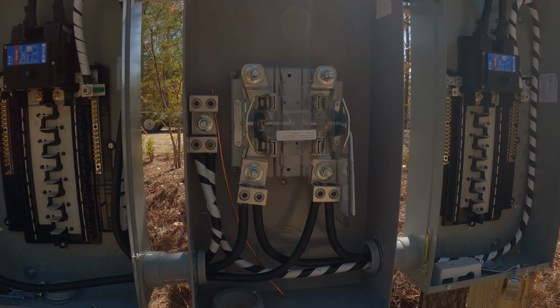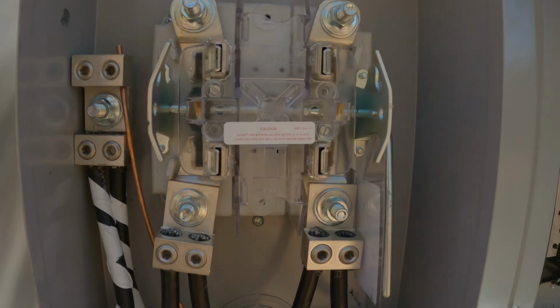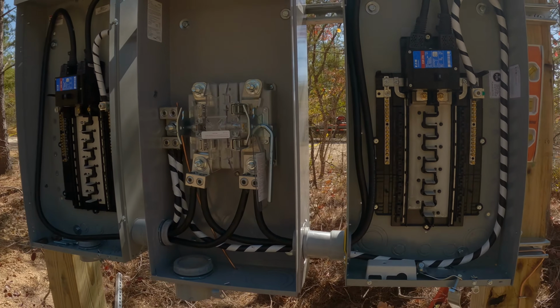Once that's all done, the ground wires are in, the wires run from the meter base to each of the panels, the panels are mounted correctly, there's Unistrut mounted behind the panels, and also Unistrut on the conduit below the panels to secure it. Then it can be inspected.